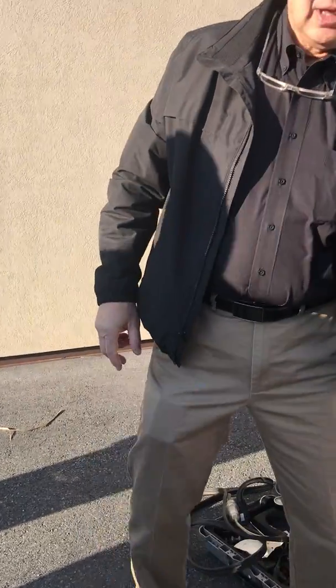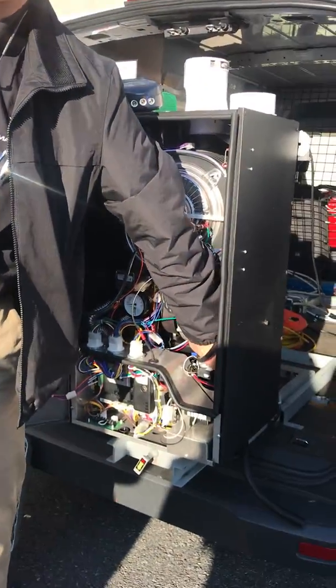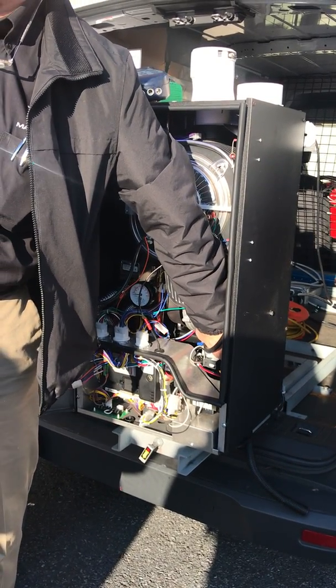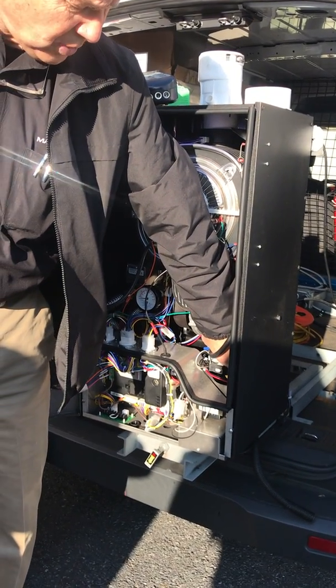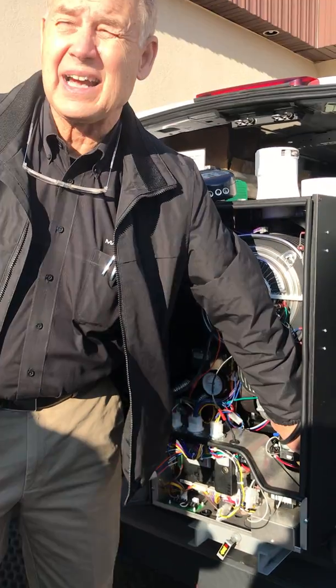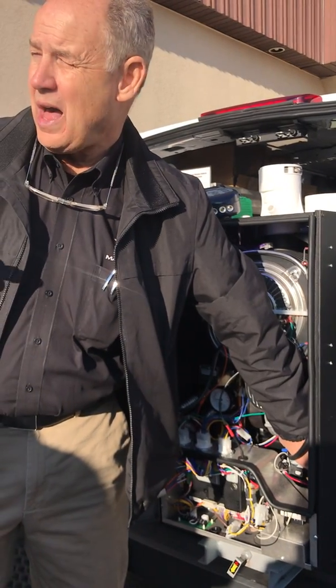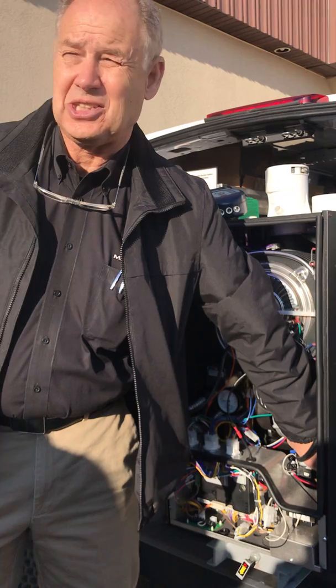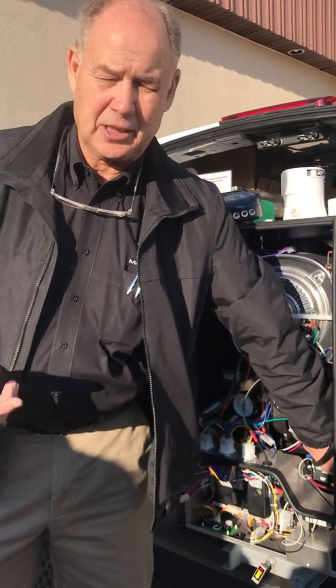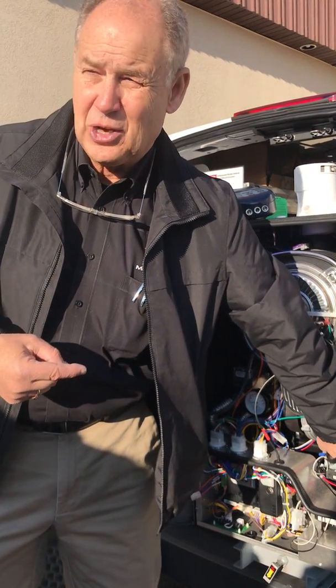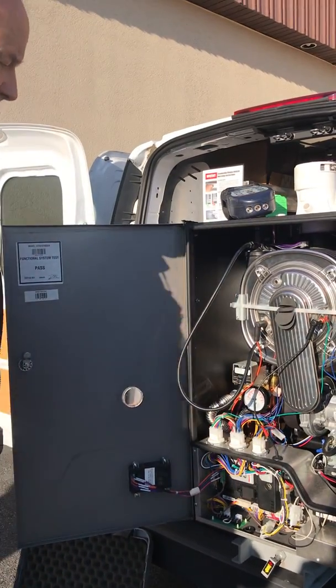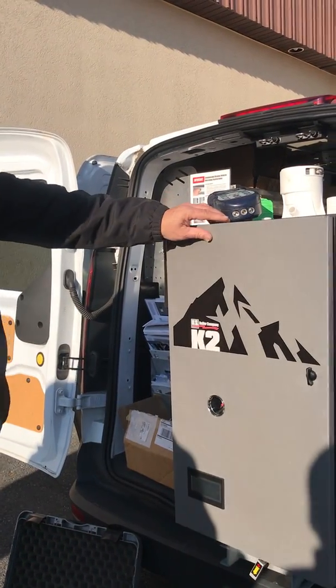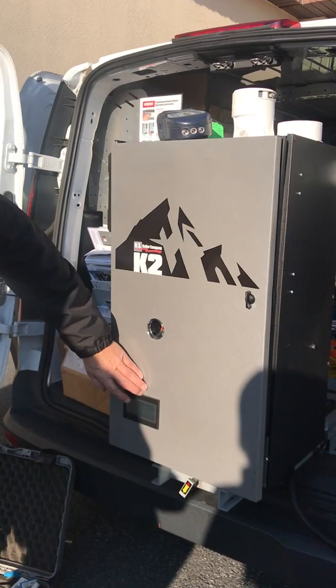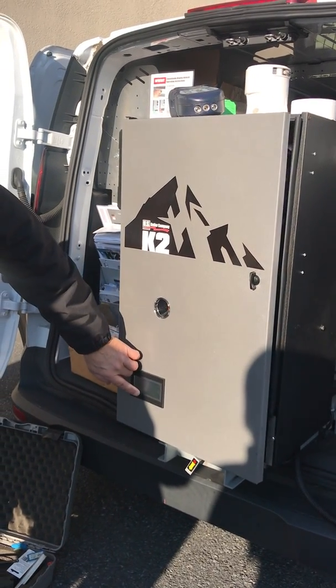What I do, usually when it goes through direct ignition, this will make sense upstairs when I show you this. When you go through direct ignition, I'll feel the click in the valve. So instead of pulling meters out, I check stuff like that. So I know that it clicks. My blower starts, I can feel the click in here. And when we go to start this up, in the control, and you'll see it upstairs, I can just hit the status button.